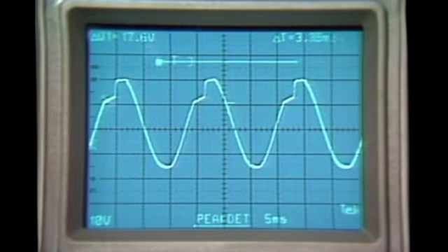The accuracy of measurements made on DSOs is greatly improved with digital cursor measurements. Measurement calculations are not made on the displayed waveform, but instead the microprocessor performs these calculations on sample point data stored in the scope memory.